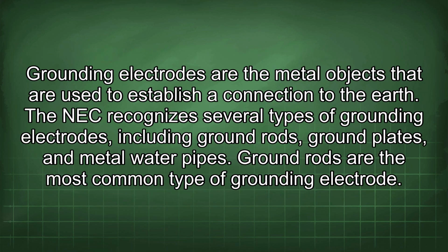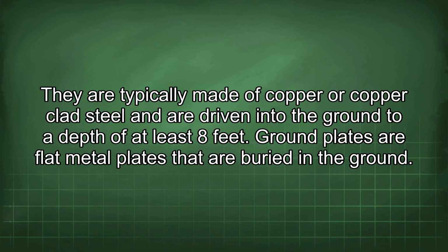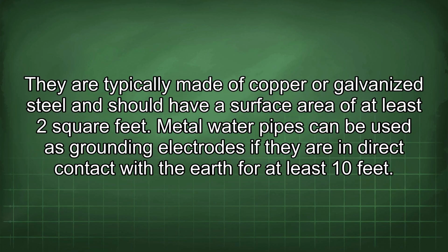Grounding electrodes are the metal objects that are used to establish a connection to the earth. The NEC recognizes several types of grounding electrodes, including ground rods, ground plates, and metal water pipes. Ground rods are the most common type of grounding electrode. They are typically made of copper or copper-clad steel and are driven into the ground to a depth of at least 8 feet. Ground plates are flat metal plates that are buried in the ground. They are typically made of copper or galvanized steel and should have a surface area of at least 2 square feet.